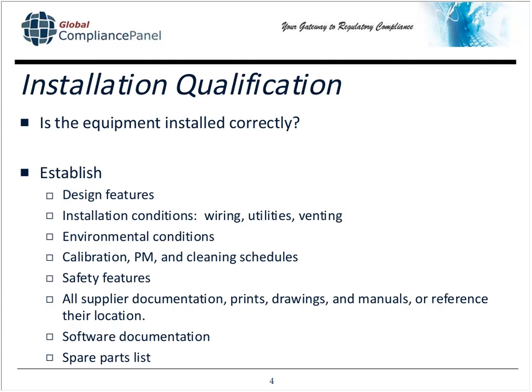And then a spare parts list. It's key to establish a spare parts list less from a regulatory compliance perspective and more from a business perspective, because you want to know what the parts are when they wear down. A good way to look at this is from looking at the PM, the preventive maintenance process supplied by the manufacturer of this piece of equipment. To determine what spare parts need to be maintained, have yourself at least one, if not multiple, of each on hand so that when they need to be replaced, you or the maintenance technician, who perhaps is an employee of the manufacturer of the equipment, can just fix it quickly to reduce your downtime.